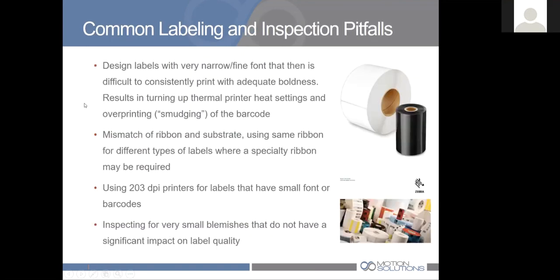So looking a little bit more at implementing an inspection system, what are some pitfalls? We've seen manufacturers who are using a very narrow or fine font that becomes difficult to consistently print legibly with adequate boldness. So the operator then may turn up the heat settings, for example, on a thermal printer, and that would result in overprinting or smudging of the barcode or other information on the label.